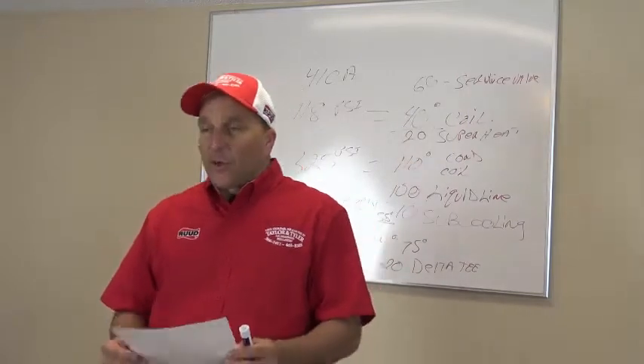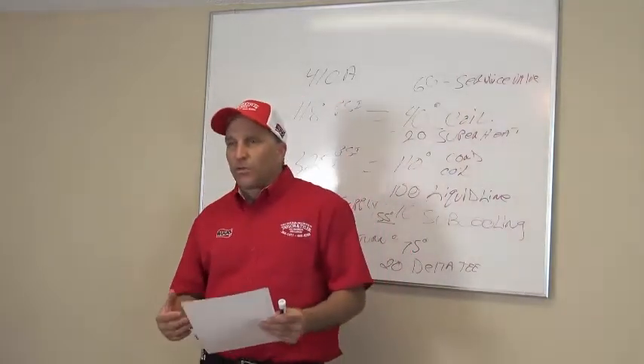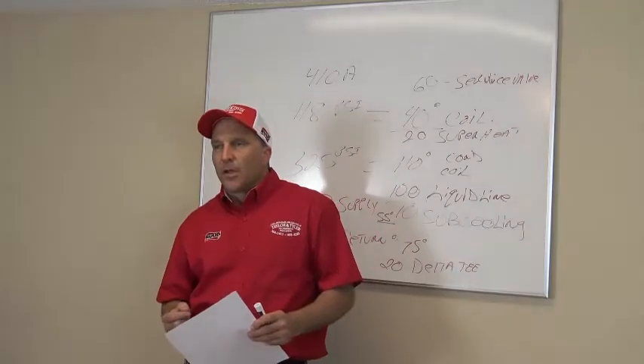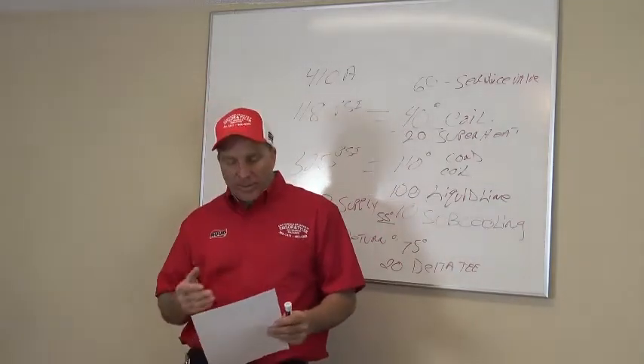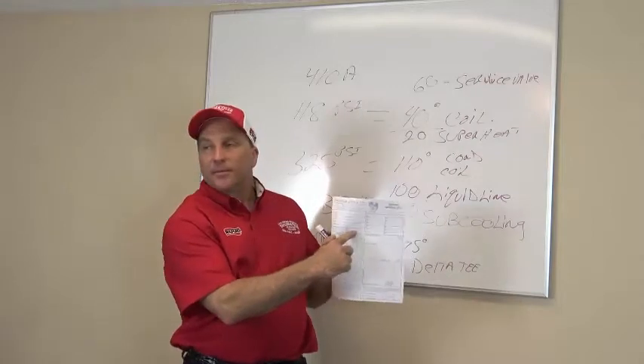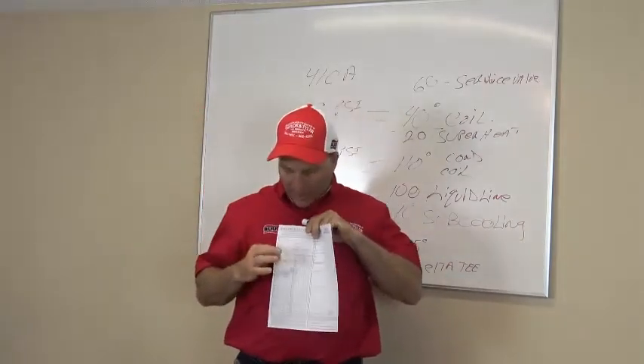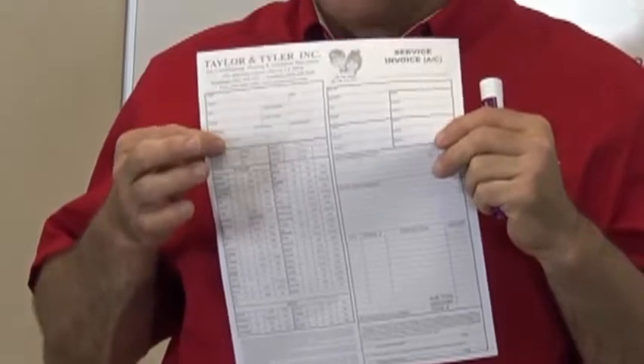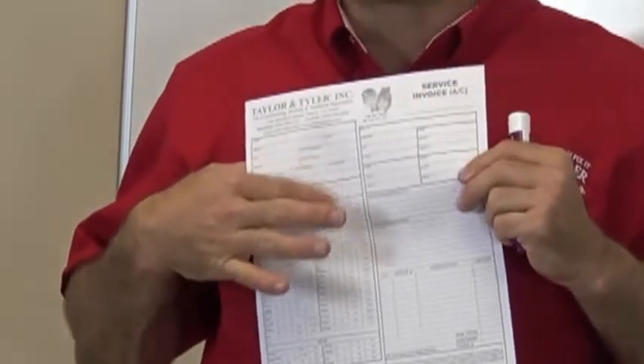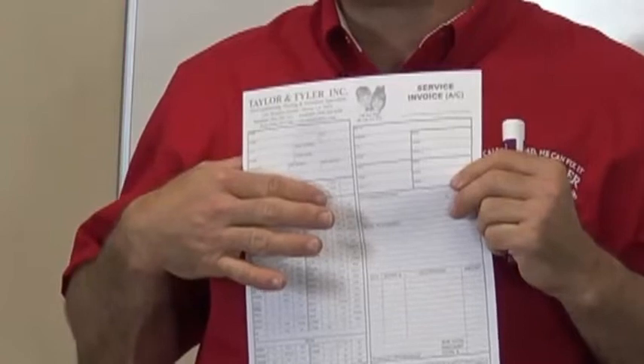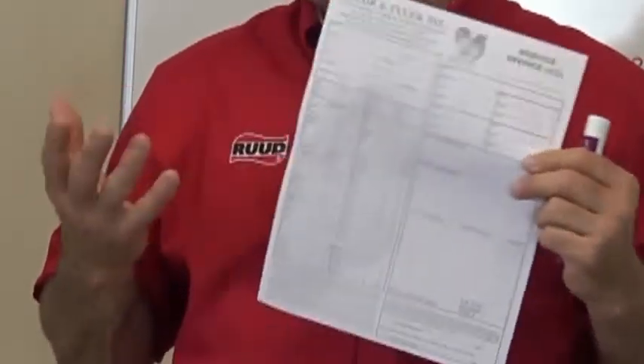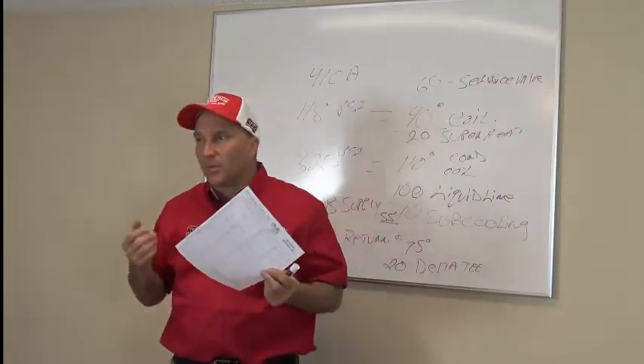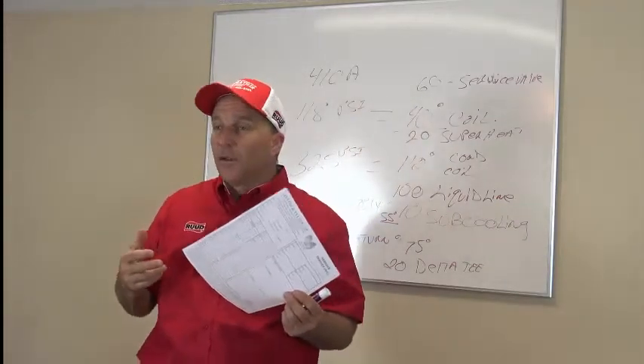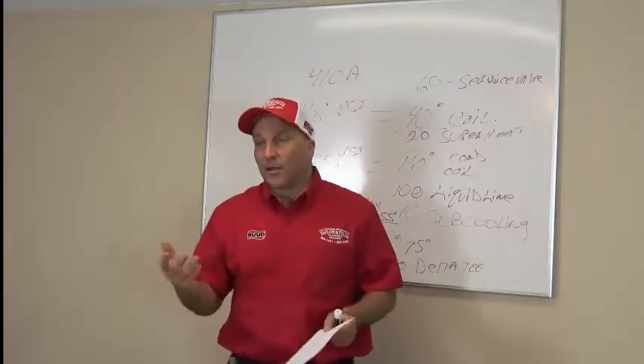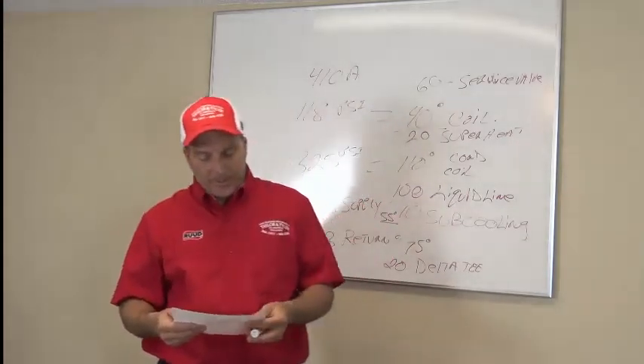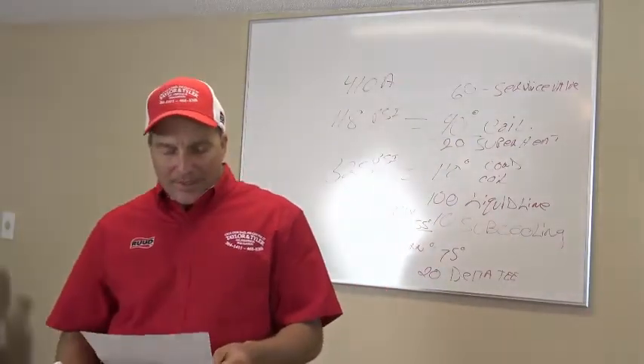So now, when you get to the job, on the left-hand side, I want you to fill all this out. When you leave the job, I want you to fill it all out again on the other side right here. Okay? So when you get there, I want it filled out on this side, and when you leave, I want it filled out on this side, because it's all going to change if you add refrigerant to the system or if you clean the condenser. Okay? If you clean the blower wheel, clean the condenser, add refrigerant, remove refrigerant, change the dryer, clean the evaporator coil, it's all going to change. Okay? Let's go ahead and start back on condenser coils, guys.